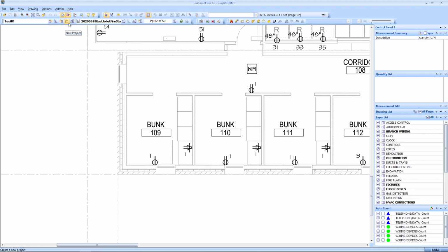When you first get this in, like I haven't set this up as a new project, but you always want to create a folder, and this is really important. It's linked to a folder. So if you happen to move the folder, you're gonna break the link. So what I would do is I would create an Accubid LiveCount folder and keep that separate from your actual bid that holds the estimate file, the .es14 or 15, whichever version you're using. Just keep those separate so you can have these folders, and it's very easy because you could just drop a drawing in there, and then if you got to do an overlay for addendum, everything's in that folder, and it's separate from the estimate itself. So it's a preference, but I would suggest you do that.